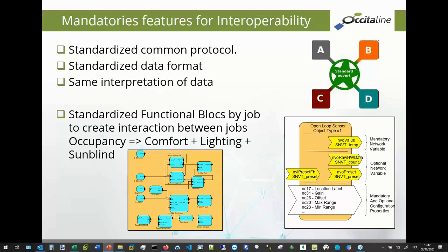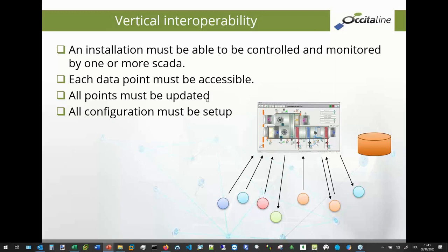The next point is very, very important for automation on the field. It's the functional block. The functional block is the most important activity in all standardized protocols. In BACnet, LON and KNX, they define functional blocks, but not with the same vision, not with the same objective. The idea is to use exactly the same sensor, for example occupancy, for comfort, lighting, and sunblind. In every protocol, like BACnet, KNX, and LON, they have a description of some data points, some properties in some cases, or some communication objects in a third protocol. And we need to create on the field some interaction between objects. This is the objective of our protocol.